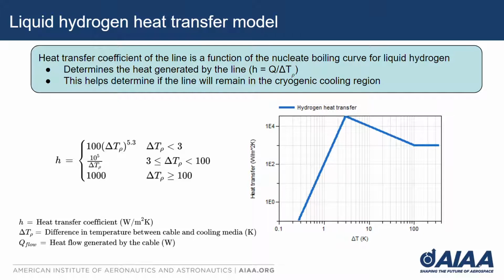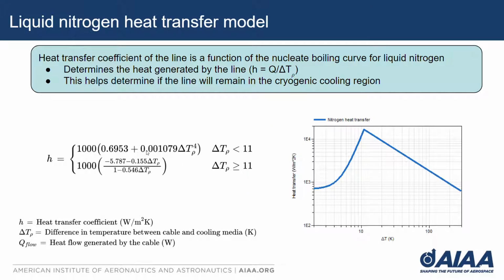We model the heat transfer coefficient as a function of the nucleate boiling curve for both liquid hydrogen and liquid nitrogen. This heat transfer coefficient determines the heat generated by the line, where H is the heat transfer coefficient, and it's a function of the heat flow generated by the cable divided by the difference in temperature between the cable and cooling media. This nucleate boiling curve produces a piecewise function for both liquid hydrogen, and here for liquid nitrogen we get this piecewise function for the heat transfer coefficient.